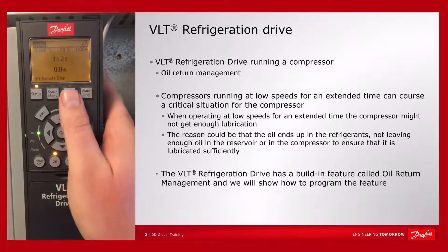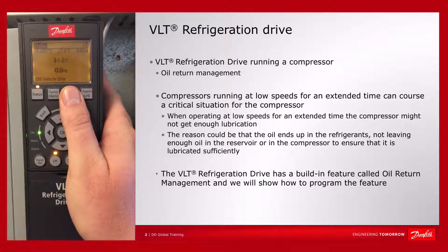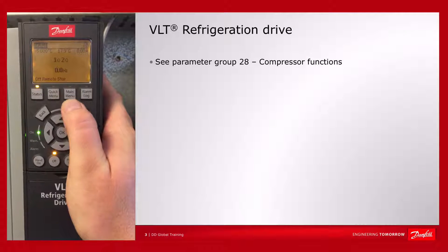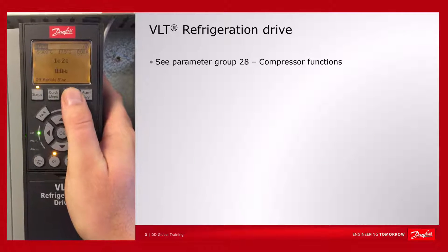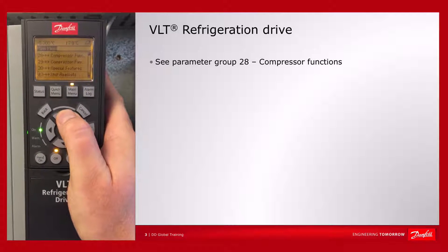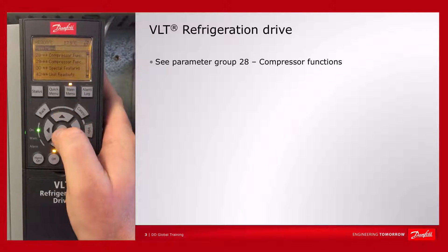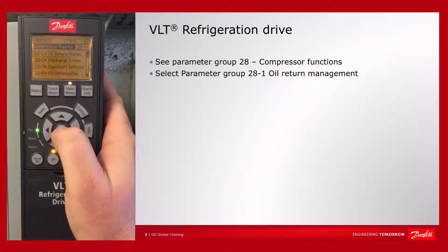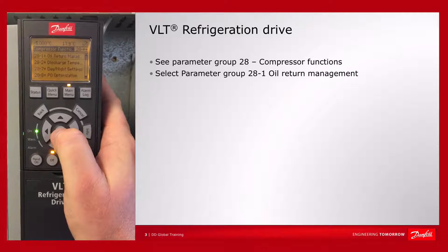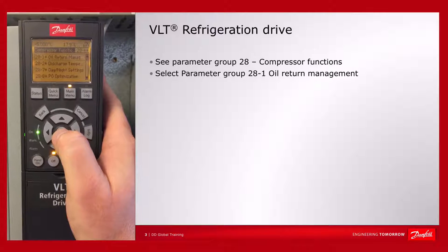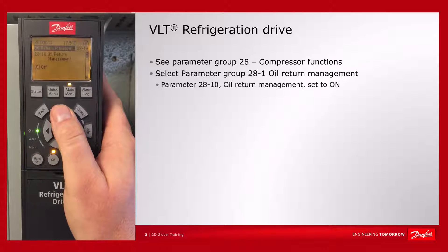The refrigeration drive has a built-in feature called oil return management and I will show you how it is programmed. Enter the main menu, go to parameter group 28 compressor functions, and select the sub-group 28.1 oil return management. You can program the feature very easily.